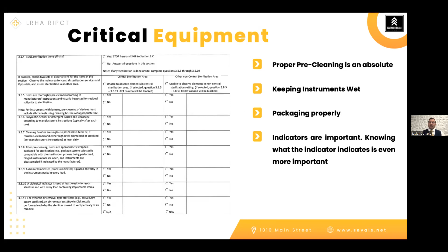Moving on to critical equipment, document. Every little step of the process, you want to make sure that you log everything. You're logging the packs, you're logging the sterilizer used, the load number, the dates, all those certain things. And you can see that in this checklist. It gives you a good reference as to what you need to be logging. But you want to make sure that you log every time that you perform sterilization or that you do anything in these areas. Storage, another issue that a lot of times we find.